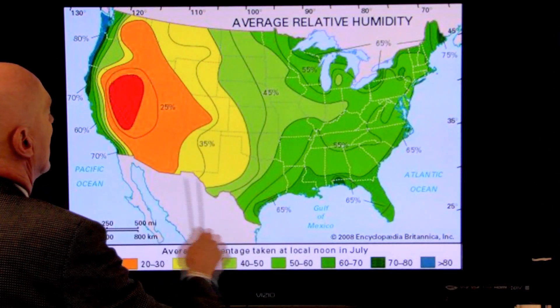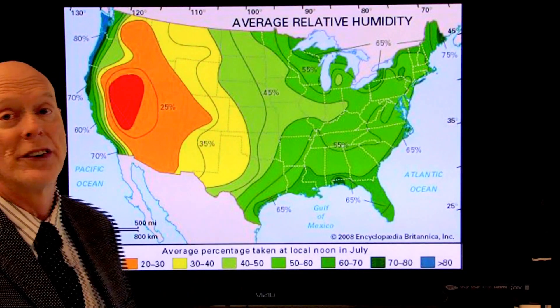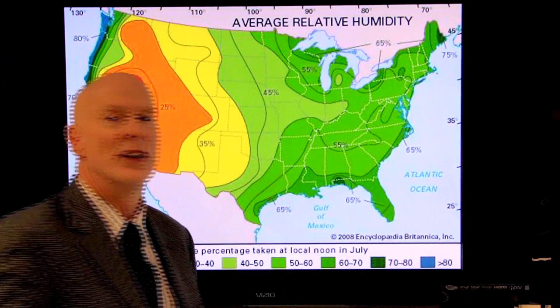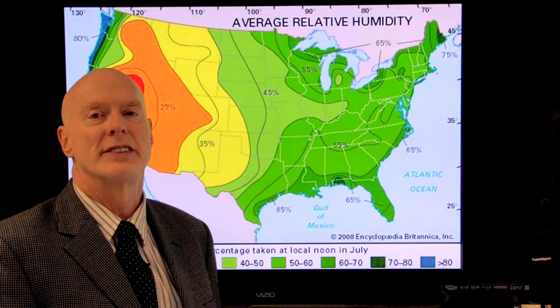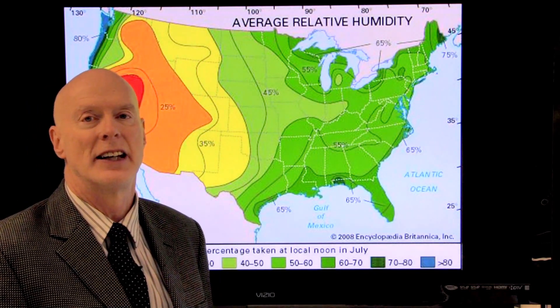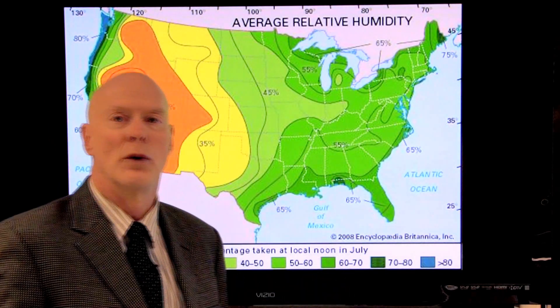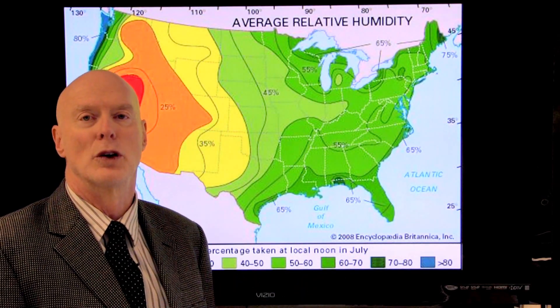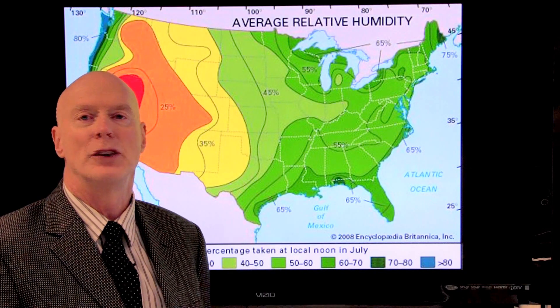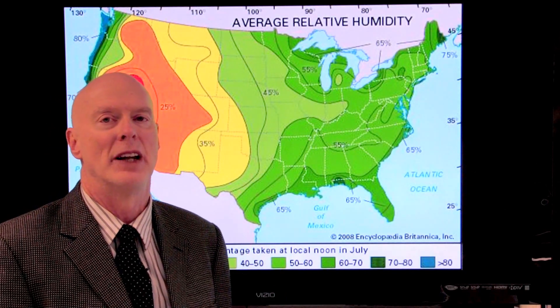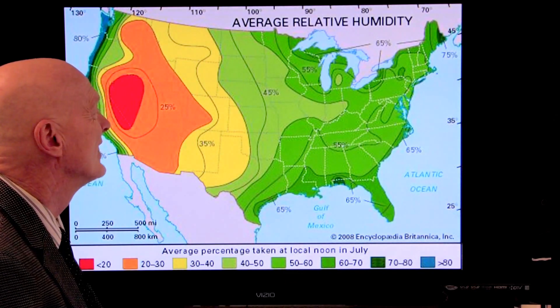A strategy for cooling in the southwest is not going to be the same strategy you use in the southeast. If you tried to cool the air with an evaporative cooler in the southeast, you could cool the air, but you'd get the air so humid that sweating would be very difficult — it would be a very uncomfortable environment. So there are two completely different strategies.